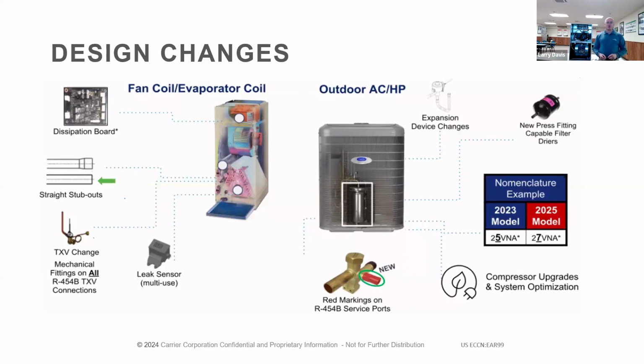If it's a heat pump, your outdoor expansion valve will be rated for the 454B. The wire going to the compressor is encapsulated, versus what we see on the current units where it's just the 3 wires going down. The wires going down to the compressor are encapsulated as part of the molded plug. You'll see a major change in the model number nomenclature. For example, for Carrier, on a heat pump, if it was a 25, it's going to 27. If it was a 24, it's going to go to 26. So you'll see a significant identification in the model number that says, hey, this is a 454B system. The filter dryers, again, are going to be rated for the 454B and they'll have the straight stubs as well.